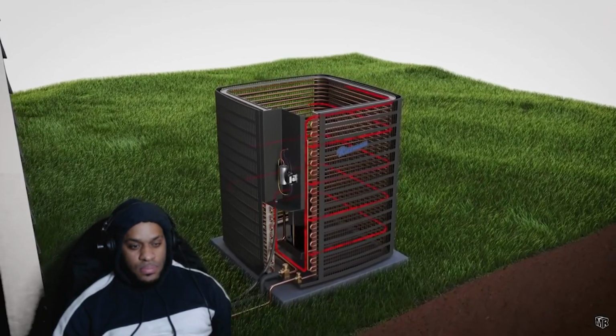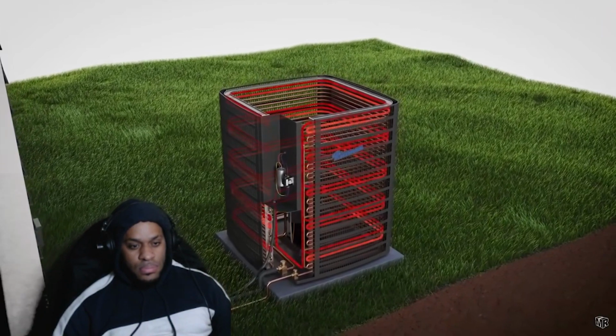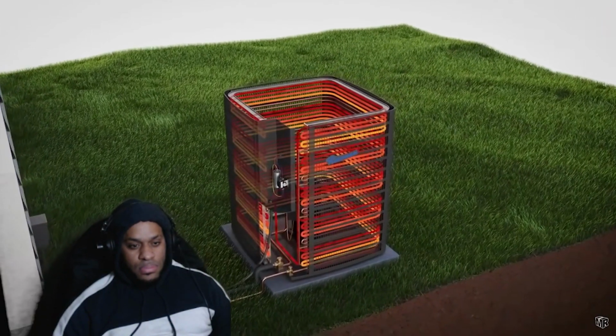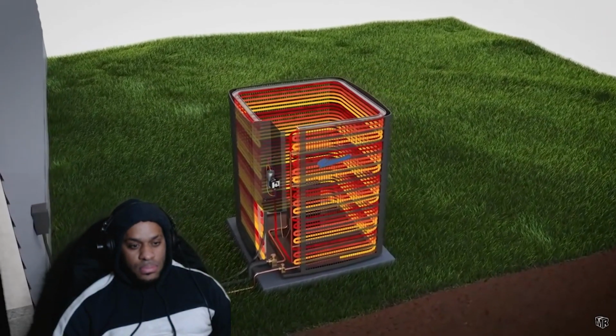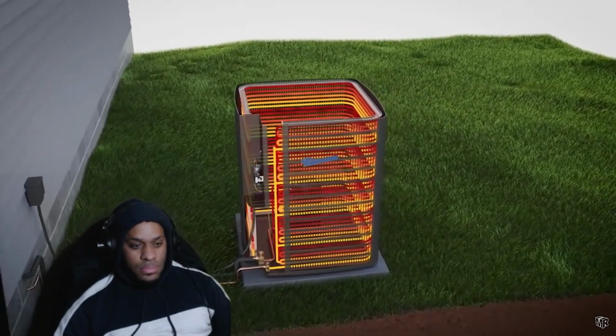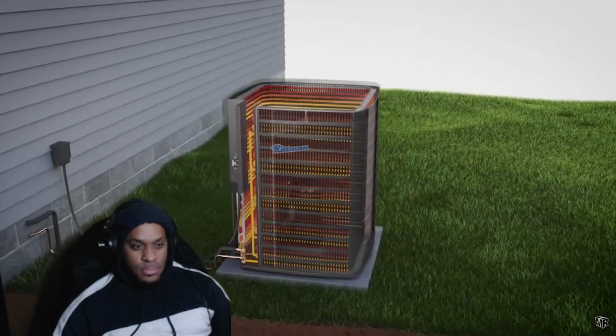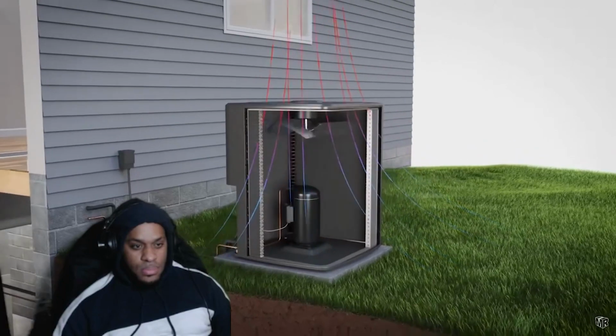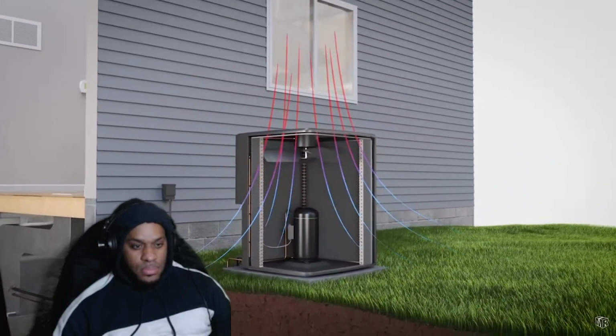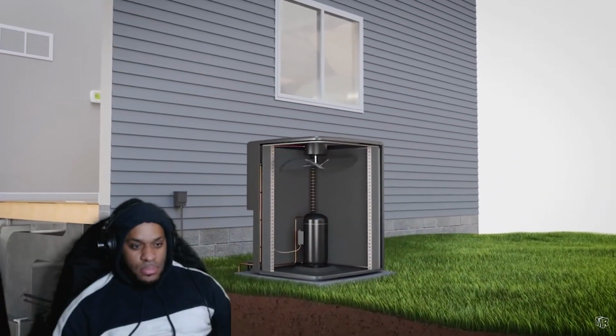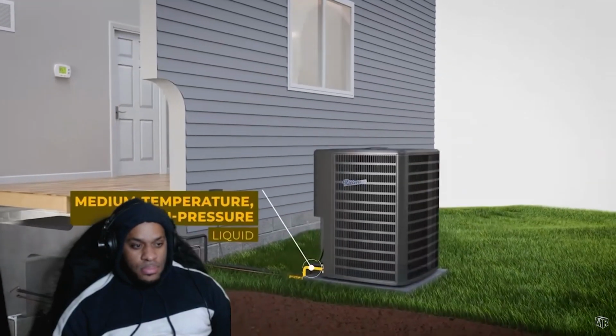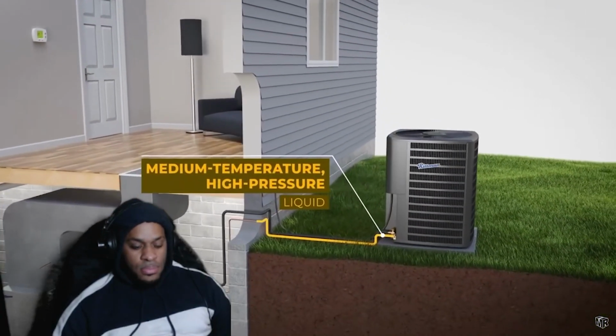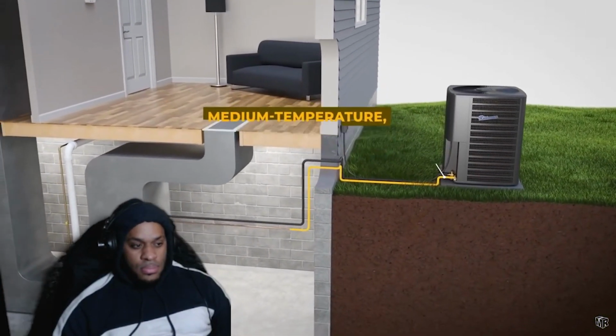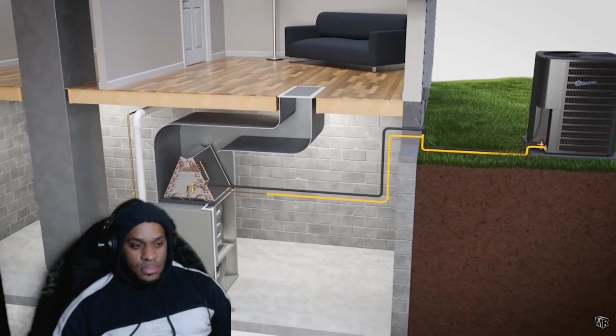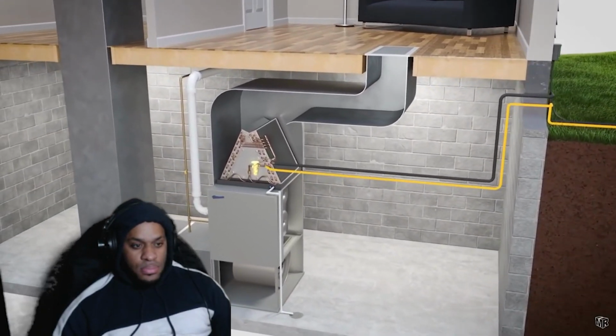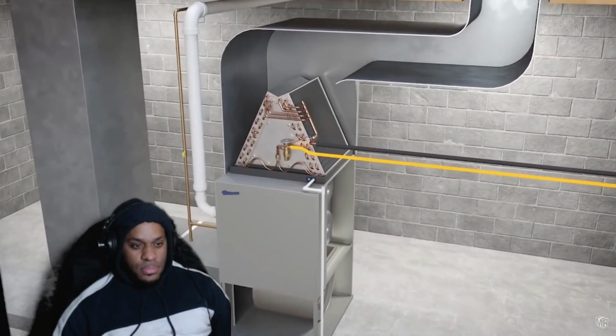It then travels through the condenser coil, where the vapor condenses into a liquid. The heat it has collected indoors and after compression is released outside. The fan inside the unit helps with this process. The refrigerant leaves the condenser as a medium temperature, high pressure liquid, then flows to the metering device. In this case, a thermal expansion valve is used.